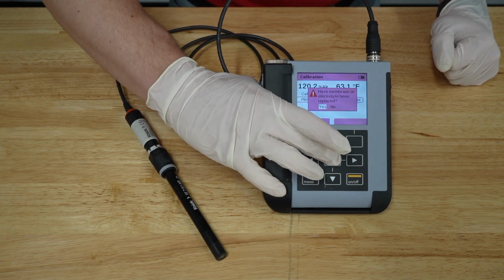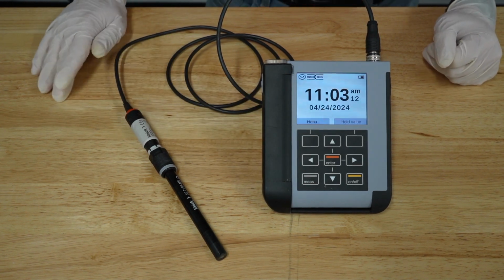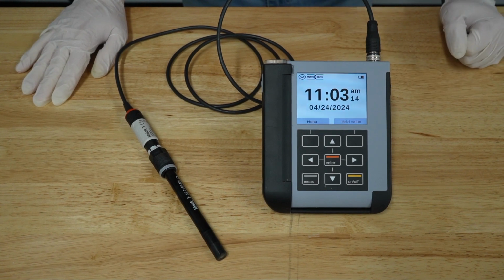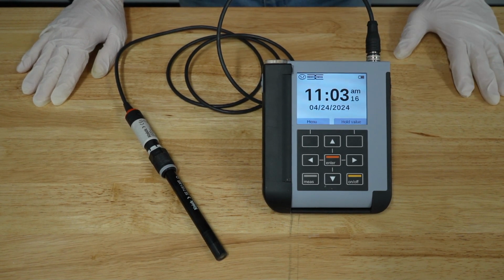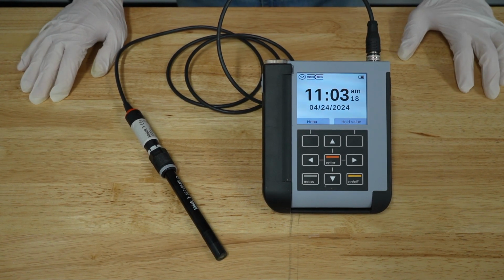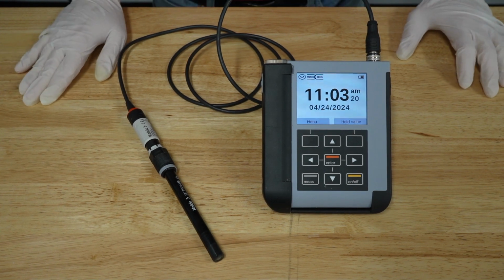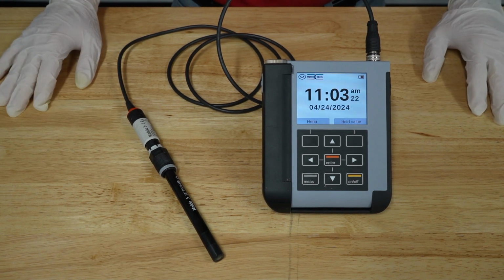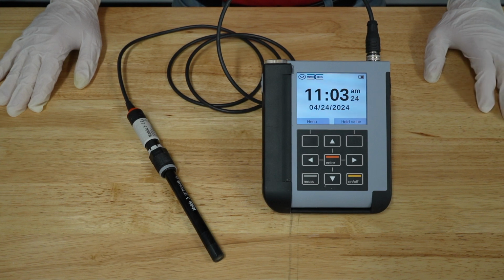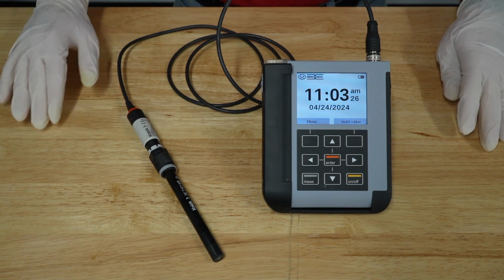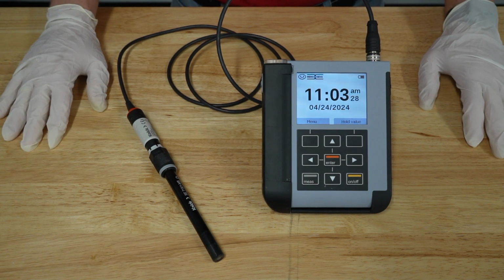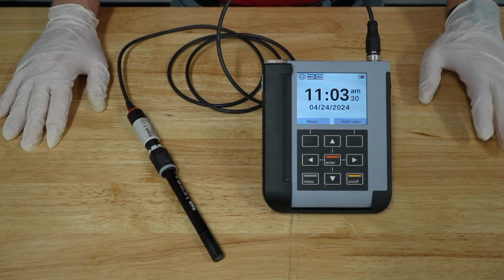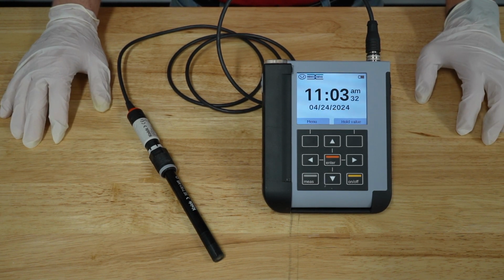I'll click yes. This resets the wear percentage on the sensor cap. Now the sensor is not ready to be recalibrated yet—we need to polarize it for at least 6 hours after being connected to a power source. Once that's done, we'll be able to calibrate the sensor accurately. Doing it before that could cause drift or inaccurate calibration.